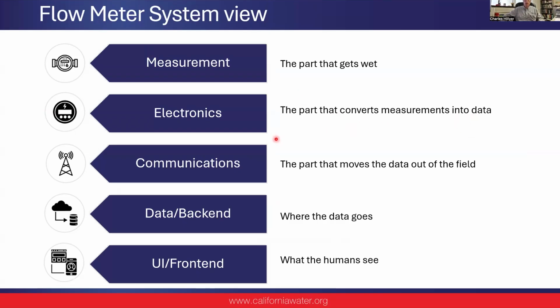There's going to be a communications element, oftentimes called the telemetry, and that moves the data out of the field. If it's only in the field, it's not particularly useful because you've got to go out there to get it. So having a communications component is very, very useful, in fact essential, in a telemetered metering system. Now, when that data leaves the field, it's got to go somewhere. Typically, it goes into a database, and I'm calling that here the data or the backend, right? So you don't actually look at the database itself. You look at what's called the front end, or the user interface. This is basically what you see, right?